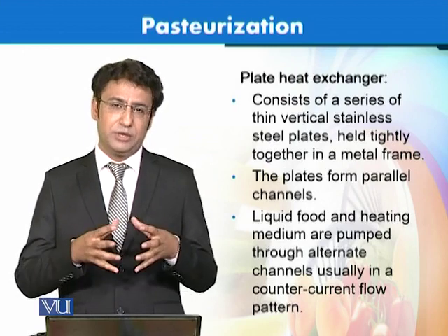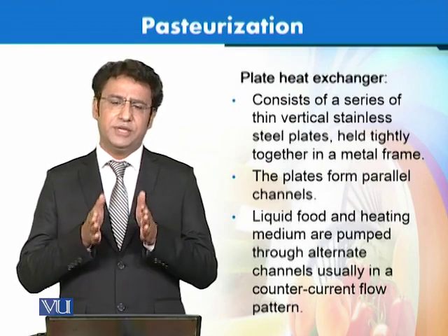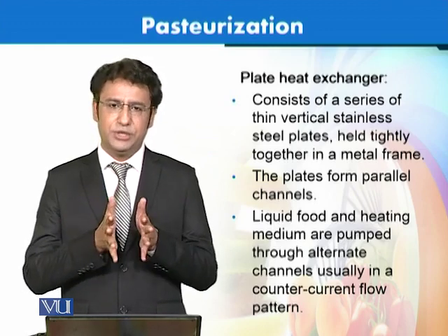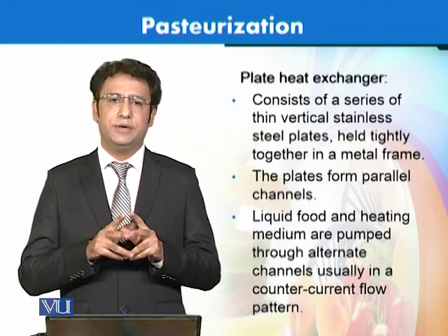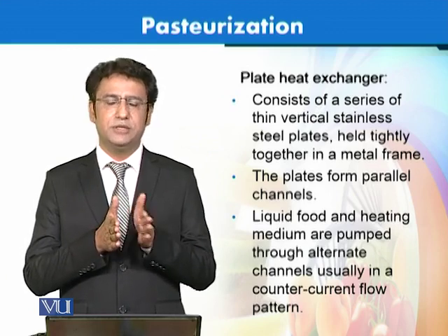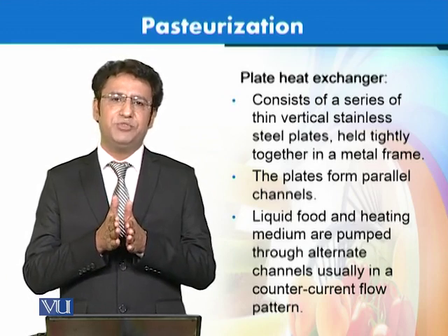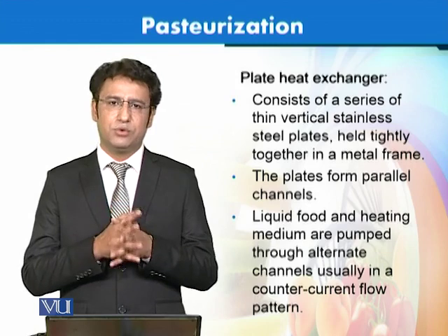If we talk about what plate heat exchangers are, they have a series of thin plates. They are vertically attached to each other, very closely, well knitted, and there are alternate plates, one for the food that has to be pasteurized, another one for the heating medium or cooling medium. Generally, steam or hot water is used for heating, and cold water is used for cooling.